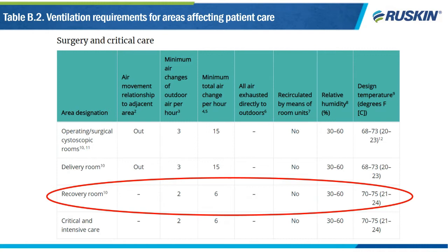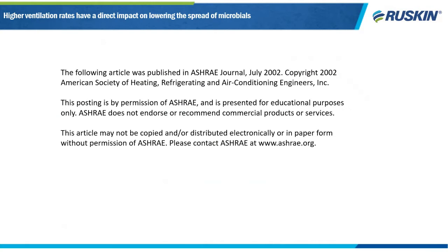Take the cubic feet of space of the room, multiply that times 6, and that would be the amount of air that's supplied. And of that, 33% should be coming directly from outside. Of course, it's conditioned, but that's how we do it. So we know that increased ventilation rates produce healthier working environments.